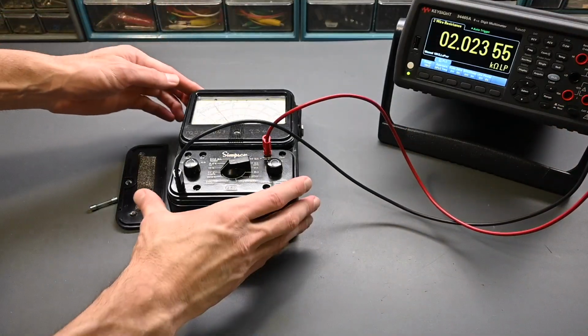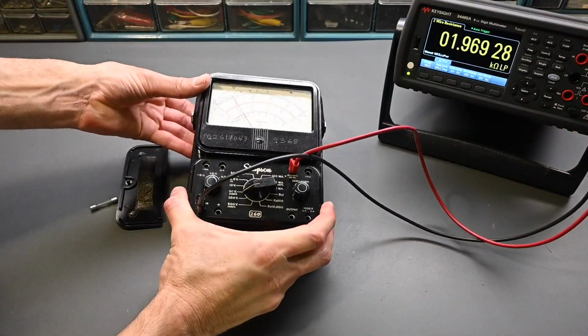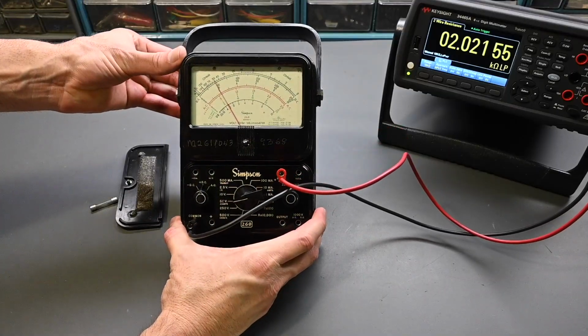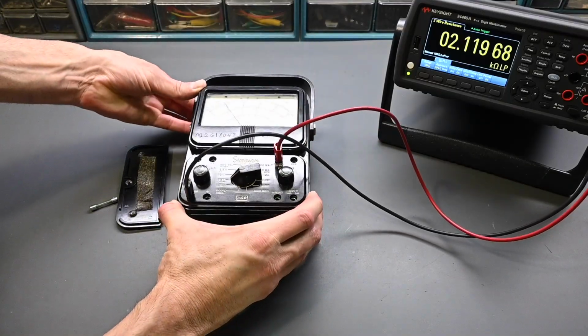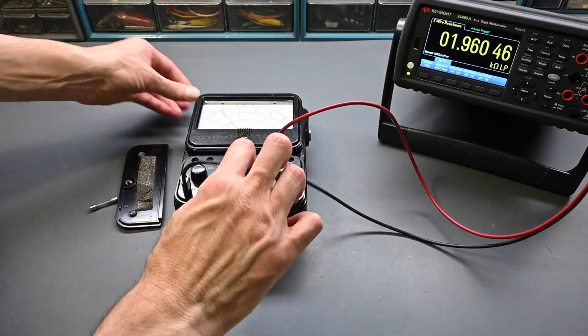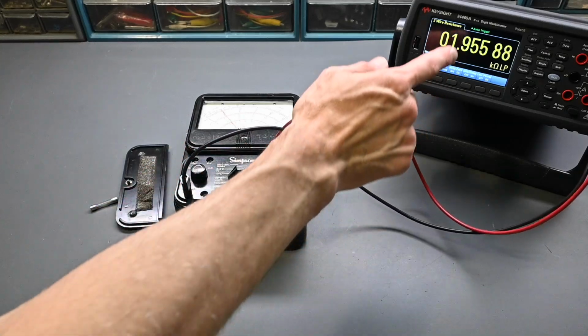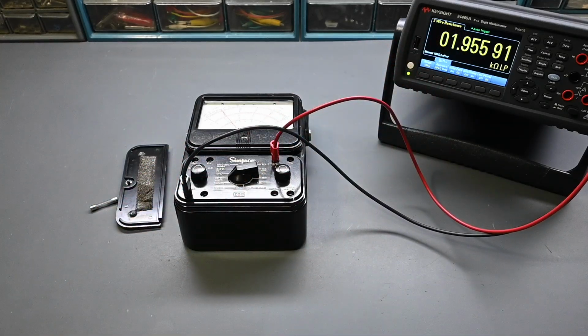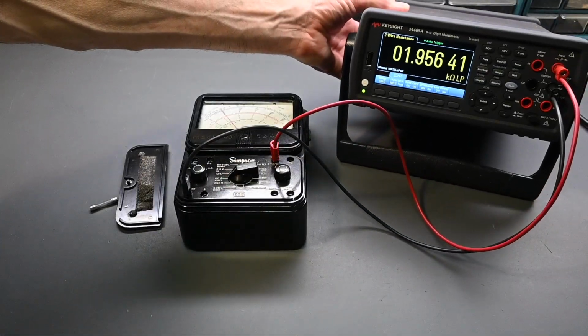All right, there we go. You can see a little bit of indication on the meter. But right away you can see that's reading just shy of 2,000 ohms, 2K ohms, and that's actually not right. That should be reading very, very close to 5,000 ohms. Make sure you put this all the way over here so you can see that.